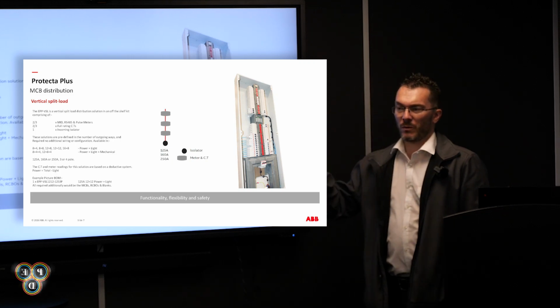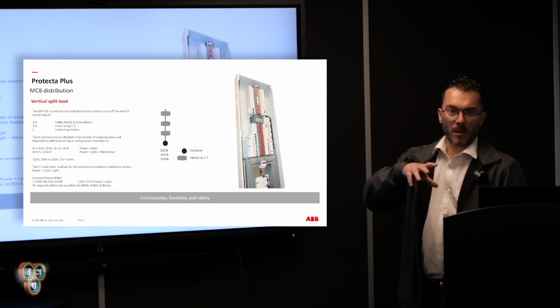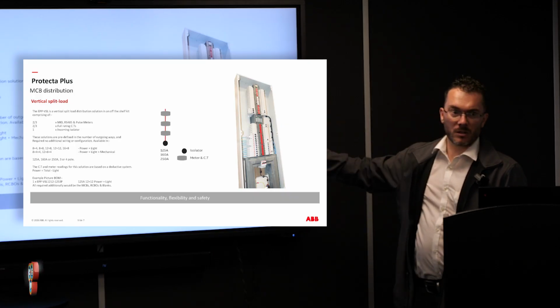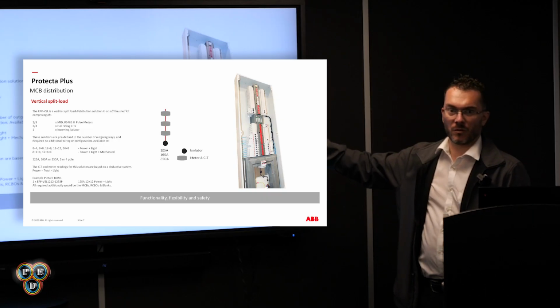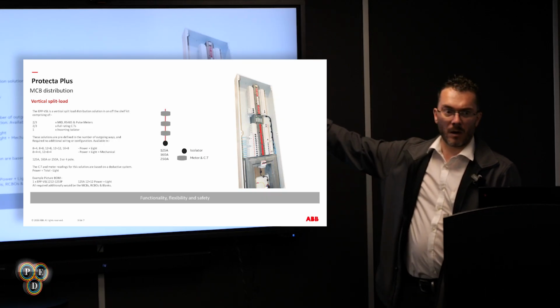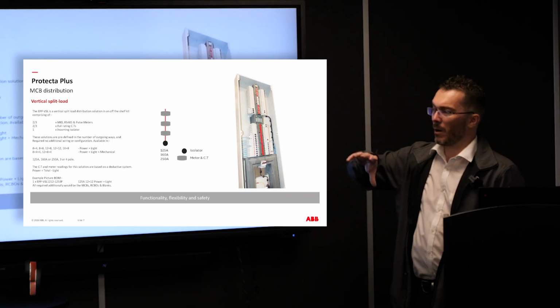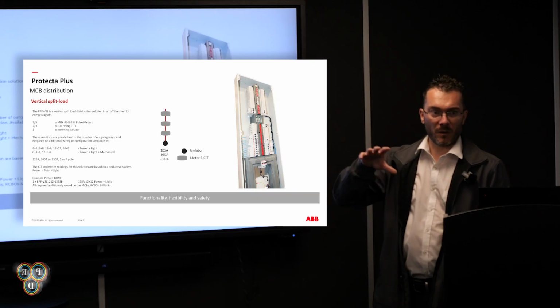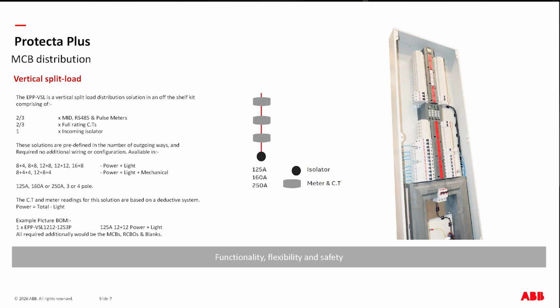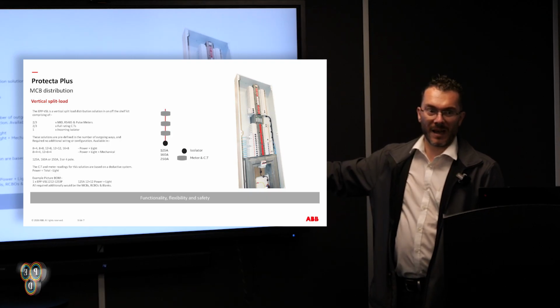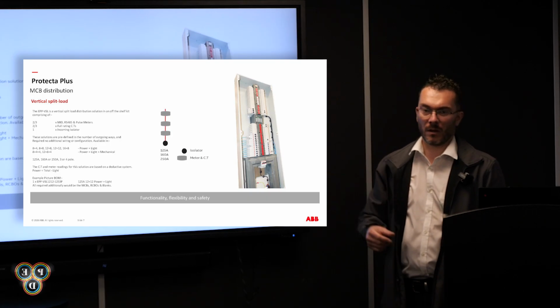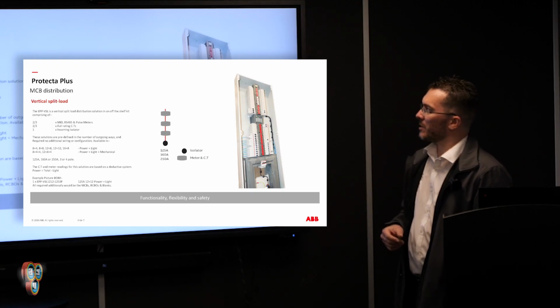Again, we've got fabrication, as Andrew's alluded to, at our facility. So we get the carcass of these and then we mount this all ourselves within the distribution boards. These are vertical split load power lighting boards. We've also got a power, lighting and mechanical option as well. Depending on whether you want to monitor the mechanical side, you get 3 meters. These will come pre-fitted with the incomer. So you decide which size incomer you want, whether you want 3 or 4 pole, whether you want 125, 160 or 250. But this will come installed with the incomer and the meters already pre-configured and tested. So you get a test certification sheet, so that we've tested it before it leaves the warehouse.